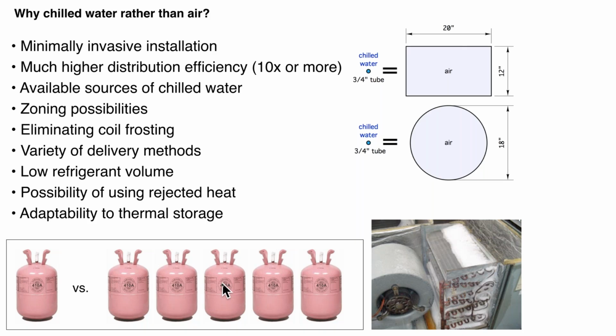Obviously that is a cost issue. It's also a safety issue if that refrigerant leaks and has to be replaced. And it's also a global warming issue. We don't want to vent or lose refrigerant. So a 4-ton air to water heat pump might have 6 to 7 pounds of refrigerant. An equivalent ductless system could easily have 3 times that amount of refrigerant in it.